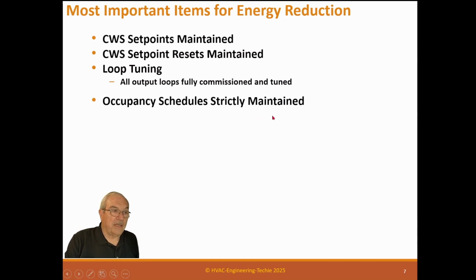Occupancy schedule strictly maintained. So in other words, what happens a lot of times is a customer will have a problem, and an operator can't figure out what's wrong and how to deal with it, so he just blows out the schedule and lets the system run 24 hours. So the next morning, that customer will be comfortable, but that just costs you a whole bunch of energy because, if you have a water-cooled system, and you want to keep one heat pump running, you have to keep the whole central plant running. So that's not an option. We should never do this. We should figure out what's wrong, find the problem, and fix it instead of trying to blow out a schedule. Sometimes they'll blow out a temperature reset schedule. We're just going to drive that condenser water down to 75 degrees, and we'll make these units work right. But at what cost? It's a high cost, so you don't want to do that.